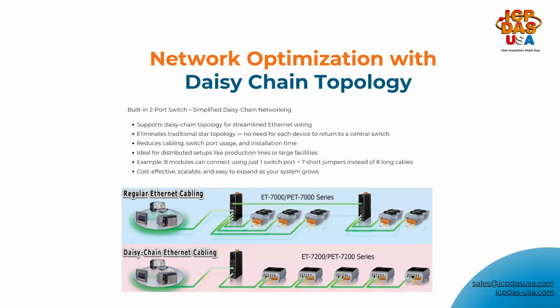Let's take a closer look at how the built-in 2-port Ethernet switch in the PET-7200 series can really streamline your network architecture, especially when you're deploying multiple I/O modules across a facility. With 2 Ethernet ports integrated directly into each module, these devices support daisy chain topology, allowing you to connect one module to the next in a linear fashion.